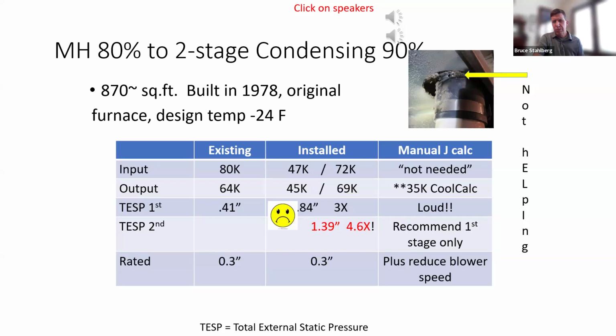In this case, we took out an old 80% furnace. The static pressure was actually pretty decent. That was the existing condition. And then we put in a high efficiency furnace, and you can see that static pressure went up to 1.4 inches. So it was very loud. And on my inspection, this is what I found.